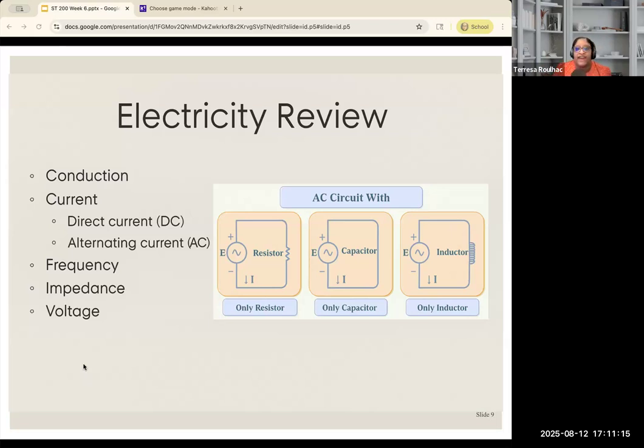Higher frequencies have a faster flow of electrons, and it makes sense because they're moving faster, like they're moving in different directions a lot faster. Now, in the operating room, high frequency current, like 500,000 hertz or more, is used in electrosurgery because it can cut or coagulate tissue without causing damage to surrounding areas. So it's not charred around, it doesn't give you that burnt scarring around it. Now, high frequency currents avoid interference with the heart or nervous system, and it reduces the risk of electrocution or cardiac arrest.